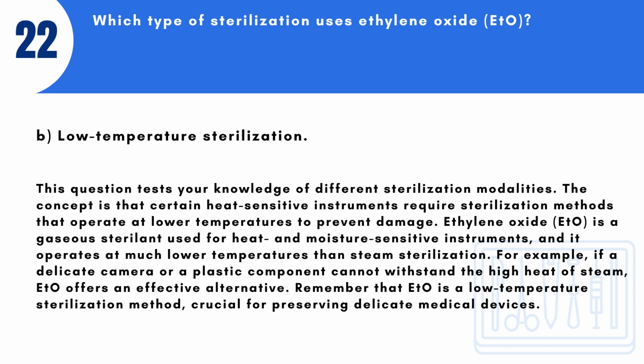The concept is that certain heat-sensitive instruments require sterilization methods that operate at lower temperatures to prevent damage. Ethylene oxide, EO, is a gaseous sterilant used for heat and moisture-sensitive instruments, and it operates at much lower temperatures than steam sterilization. For example, if a delicate camera or a plastic component cannot withstand the high heat of steam, EO offers an effective alternative. Remember that EO is a low-temperature sterilization method, crucial for preserving delicate medical devices.